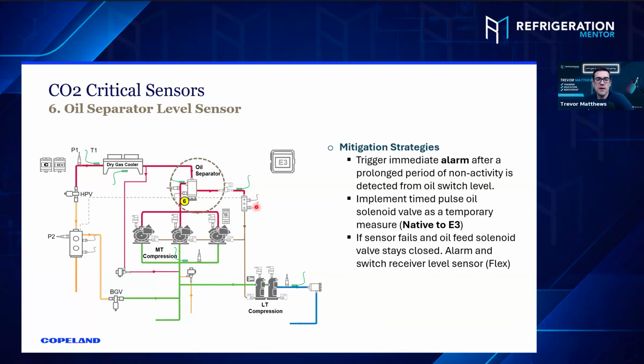The thing is, there's different brands out there. You know what I mean? Some are optical eyes, some are actual sensors in there. These are maintenance things that you need to check as well. Because if you go in and do a maintenance and you just change the coalescent filter, for example, and you don't go and clean that, that's an issue. That's on us, right? So you've got to go and check them, take them off, clean them, because these sensors can fail.